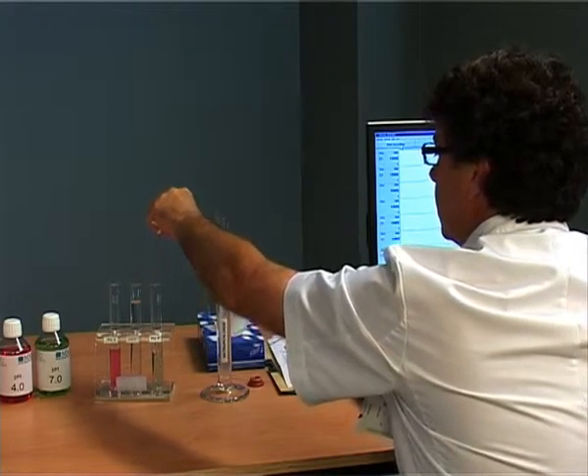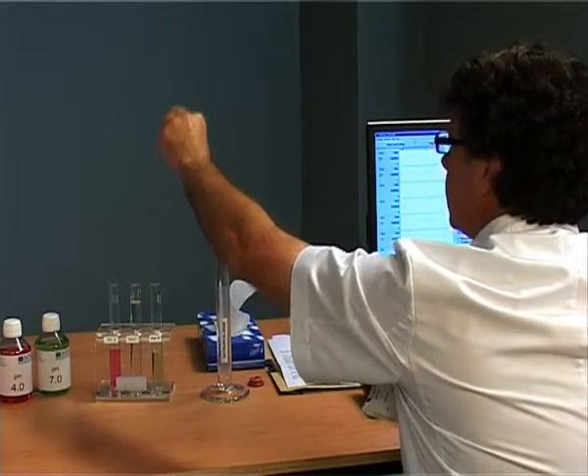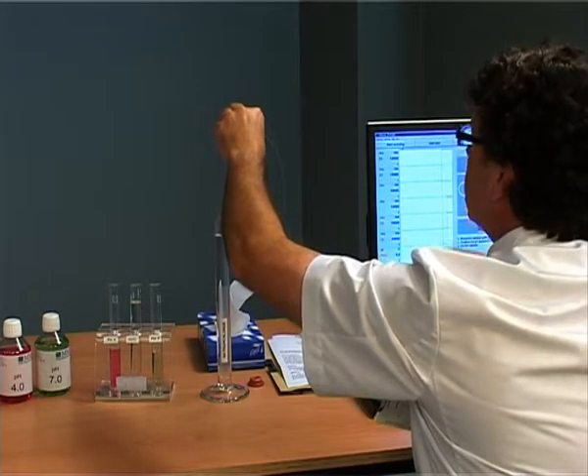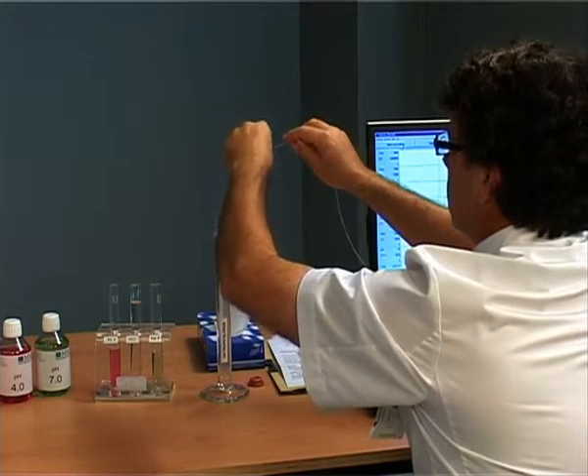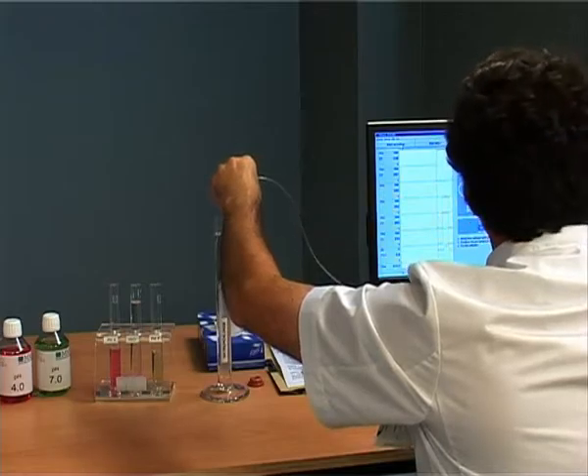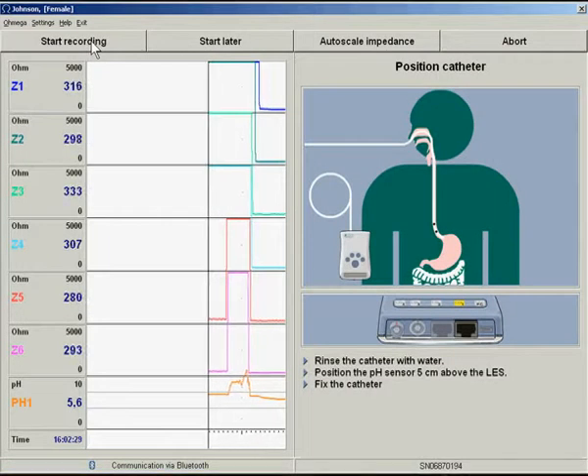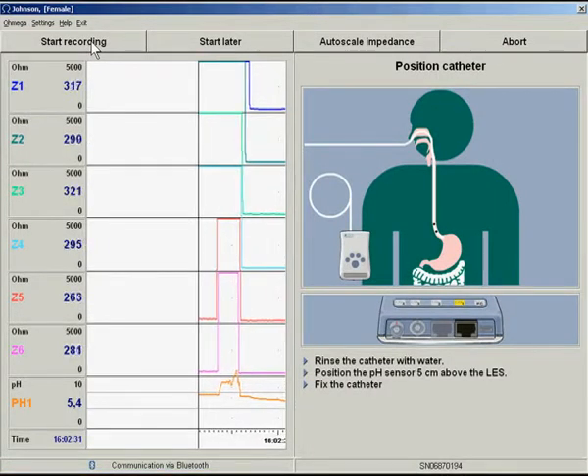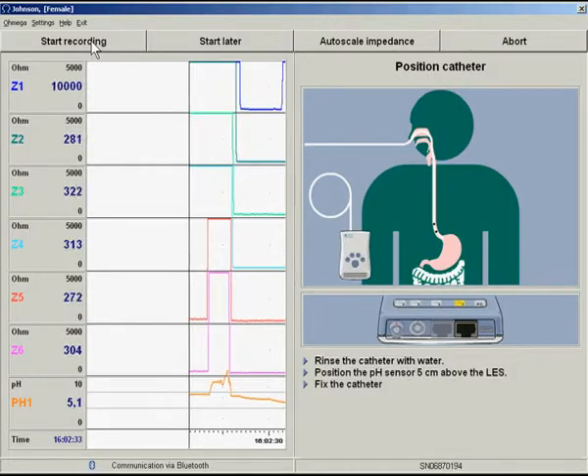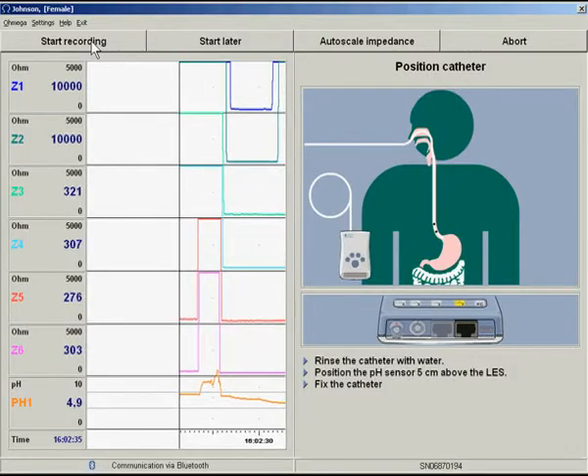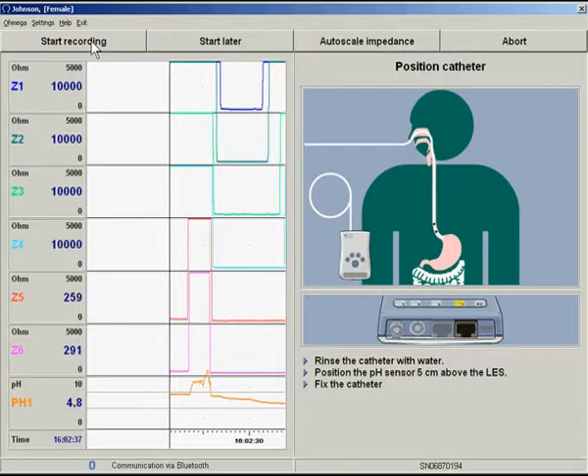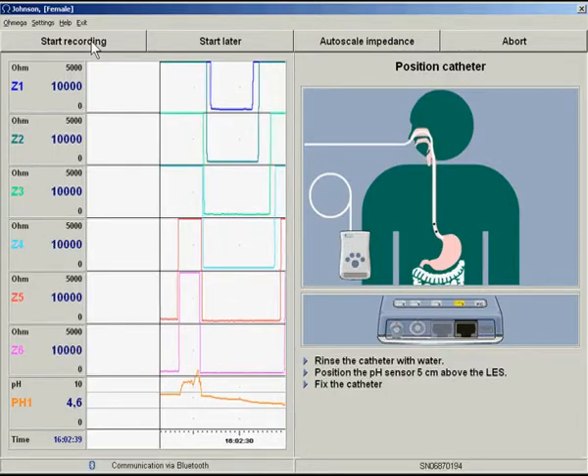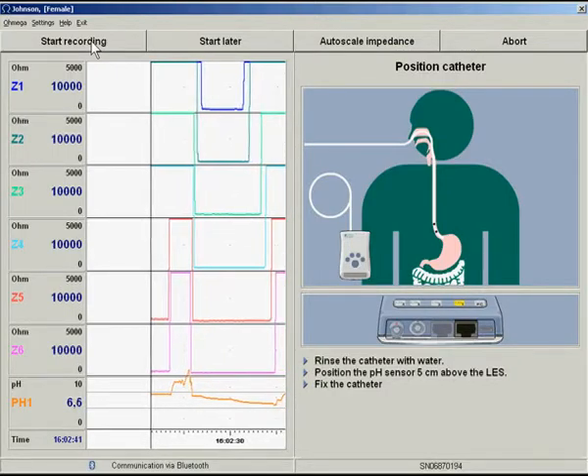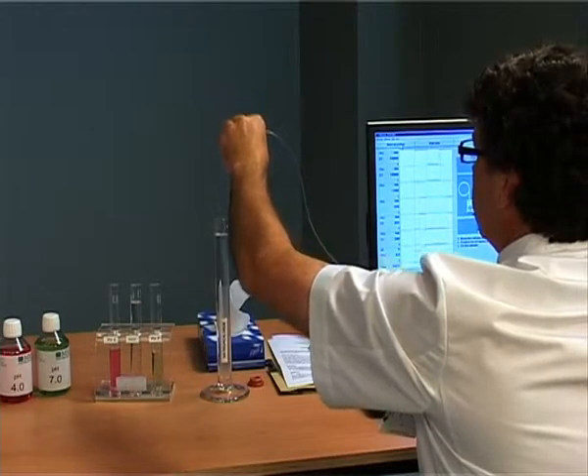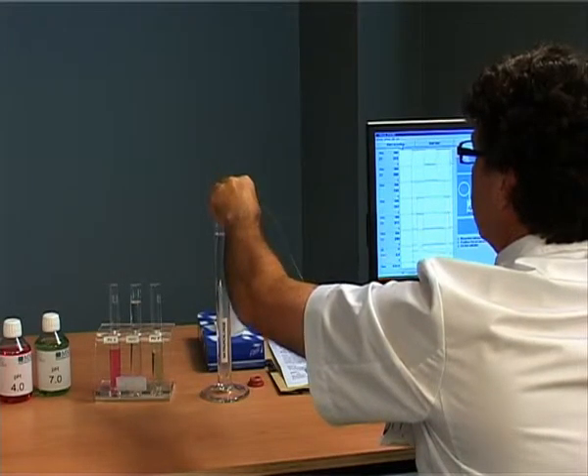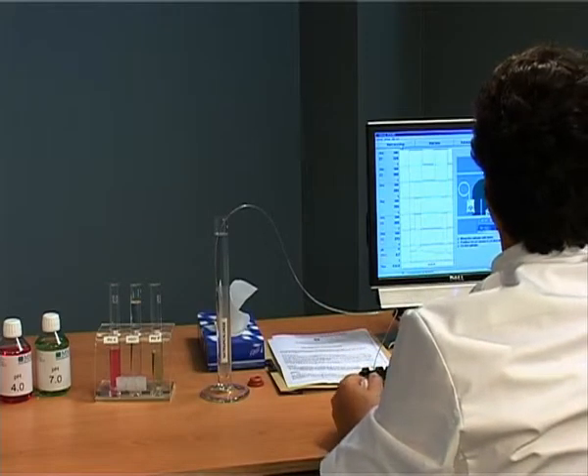Once stable pH values have been obtained, you are ready to check the quality of the impedance channels. Place the catheter in the long test tube containing saline or buffer solution. In saline, the impedance signal drops. When the catheter is removed from the test tube, impedance increases due to the contact with the air. With quality control of the pH and impedance channels, you are ready to welcome the patient.